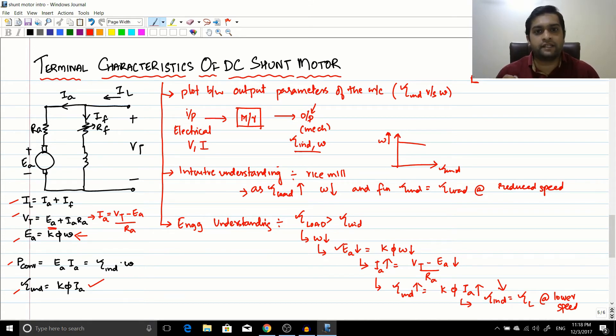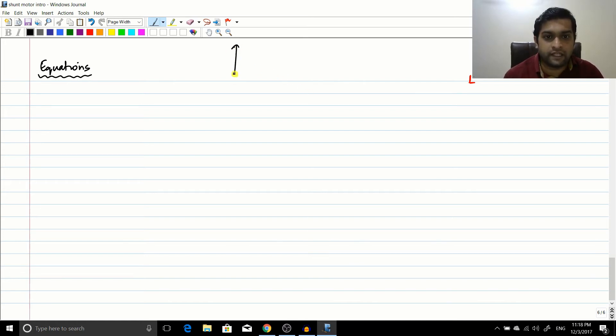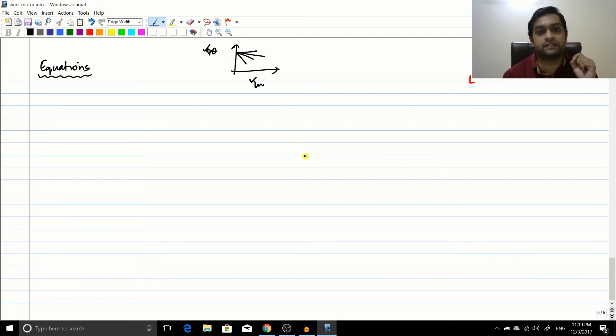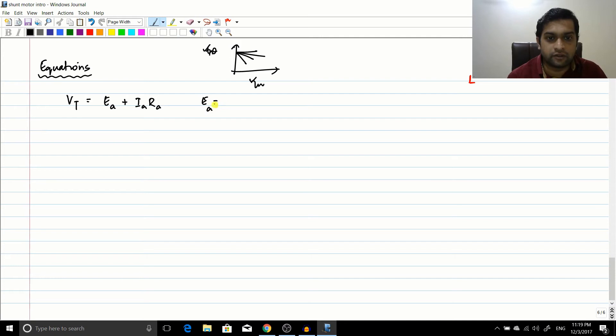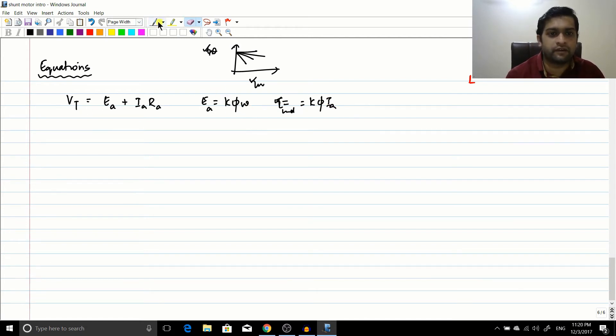You may ask why we need equations on top of the intuitive understanding. The reason is that while intuition tells us the speed-torque relation is a drooping curve, equations tell us how fast it drops. The only equations we require are: Vt = Ea + Ia·Ra, Ea = K·φ·ω, and τ_induced = K·φ·Ia.